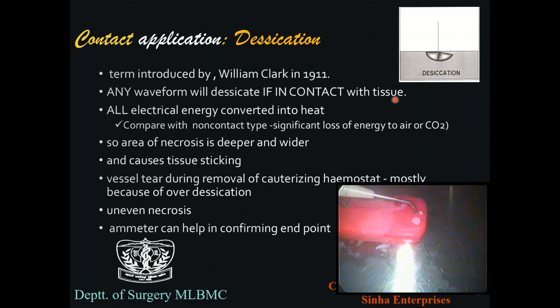So here see the probe is in contact with the tissue. All electrical energy is going to convert to heat. Now, as opposed to the non-contact, where part of the energy or the heat would be dissipated into the atmosphere, here it is going to go into the body, all of it. So when you compare to the non-contact type, here all the electrical energy is going to heat the body, and that's why the damage can be much more as opposed to the non-contact, where significant loss of energy occurs to the air. So in a contact form, the area of necrosis would be deeper and wider and would cause tissue sticking. The vessel tear during removal of the cauterizing hemostat is mostly because of over desiccation.